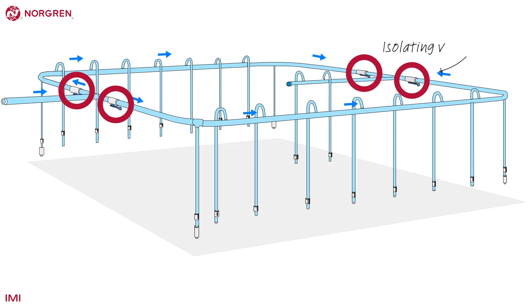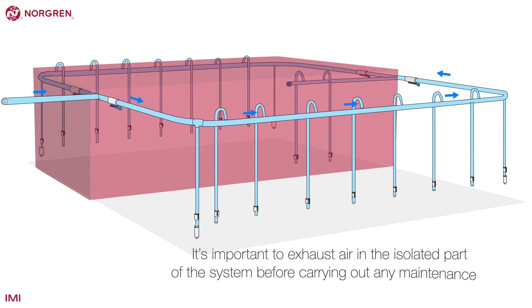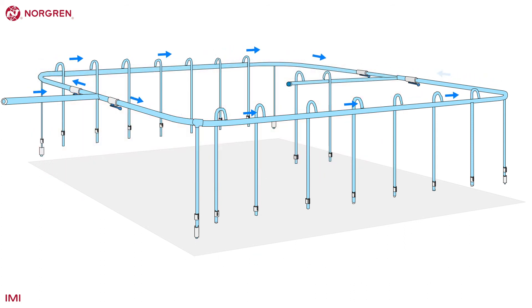There are four valves in this visualization. They are located in such a way to isolate half of the ring main, allowing maintenance or repair while the other half continues operation. It's important to exhaust air in the isolated part of the system before carrying out any maintenance.